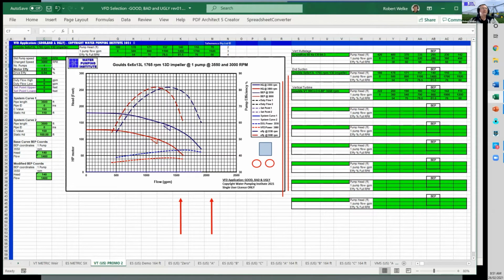Let me go back and run through a bit of a tutorial that defines where we're going. Over on the left is a system curve, so we can add one here. It's a 10-inch pipe, 3,600 feet long, with a Hazen and Williams value of 150, and a static lift of 110 feet. To guide us, we've got some flow indicators. We're going to run at 1400 gallons a minute, a fixed flow output.